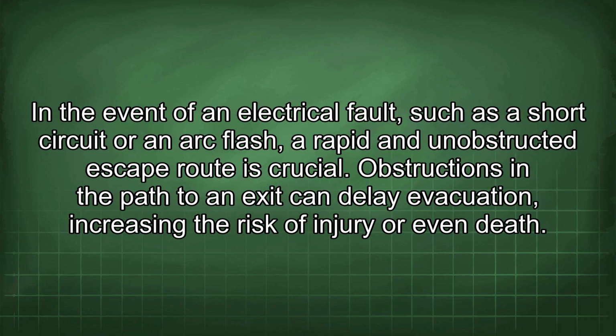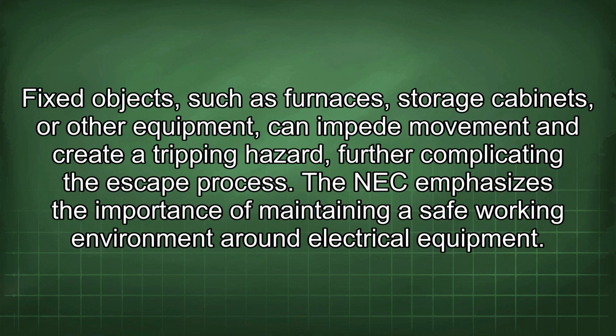In the event of an electrical fault, such as a short circuit or an arc flash, a rapid and unobstructed escape route is crucial. Obstructions in the path to an exit can delay evacuation, increasing the risk of injury or even death. Fixed objects, such as furnaces, storage cabinets, or other equipment, can impede movement and create a tripping hazard, further complicating the escape process.